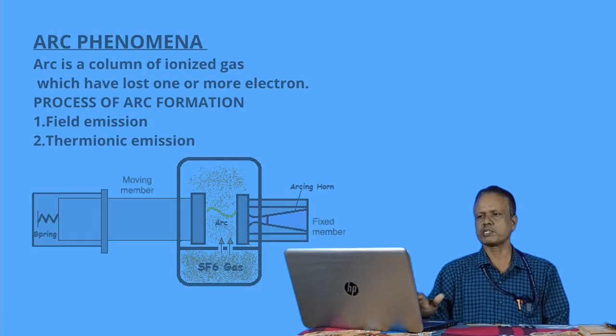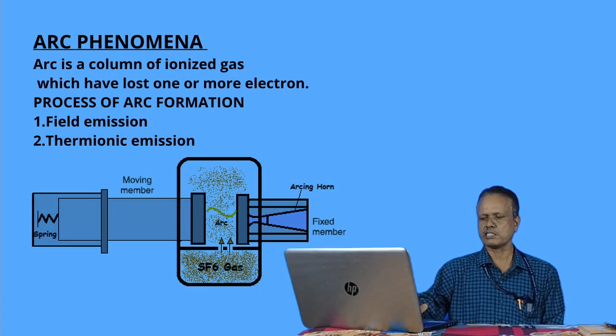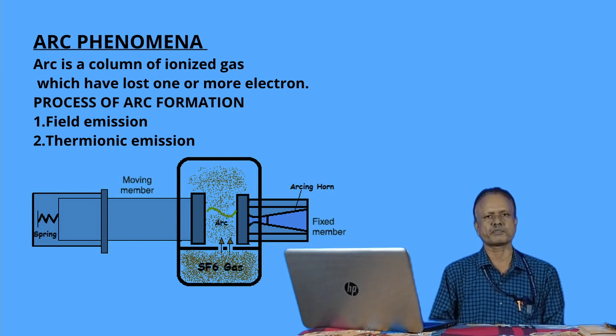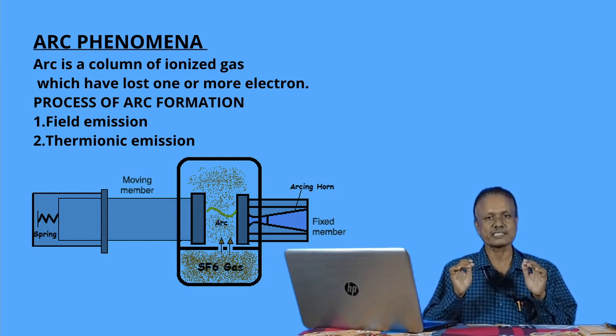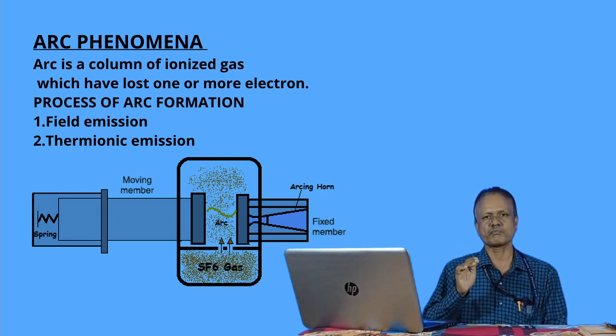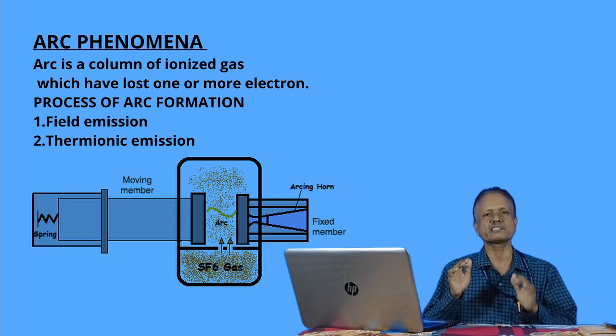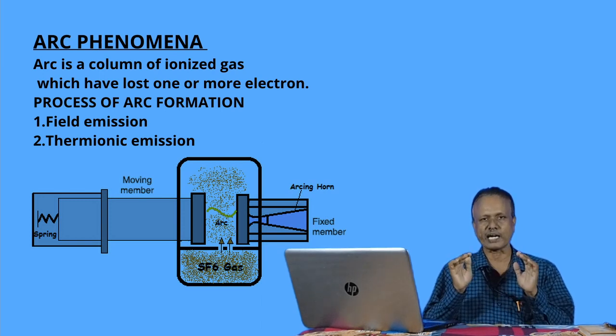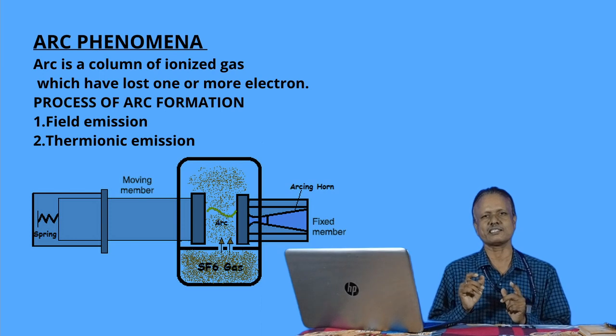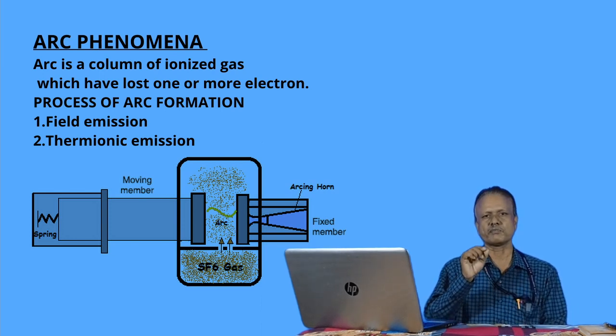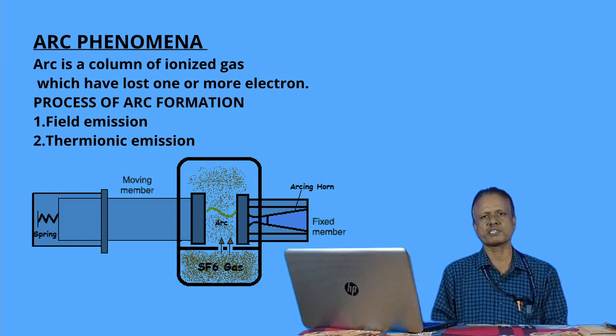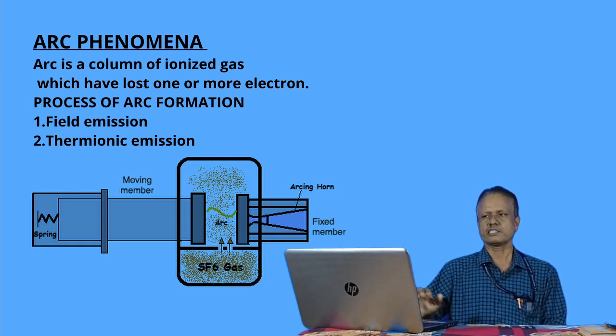Next, arcing phenomena. In this phenomena, the arc which is developed between these two contacts, these are called current carrying contacts, that is fixed contact and moving contact. So in between these two an arc is developed. How this arc develops we will discuss, but before that, what is arcing phenomena? It is the column of ionized gas, formed when some electrons are detached from the atoms of that gas, and in this way we can define it as an arc.